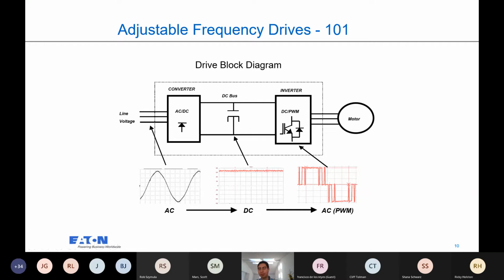This is important: because we have a VFD, it has to go directly onto your inverter-rated motor. Otherwise, you can have issues if you try to apply this into a larger system. So make sure we're going directly into the motor, the compressor, the fan, not into a system that has PLCs or other components, for example.